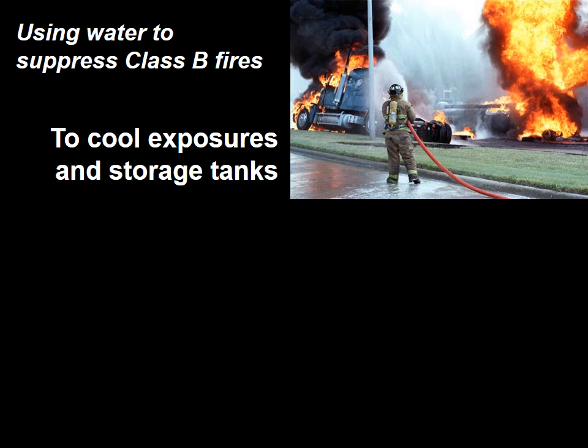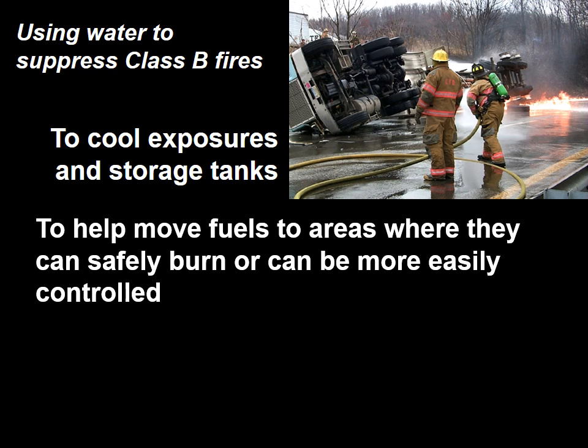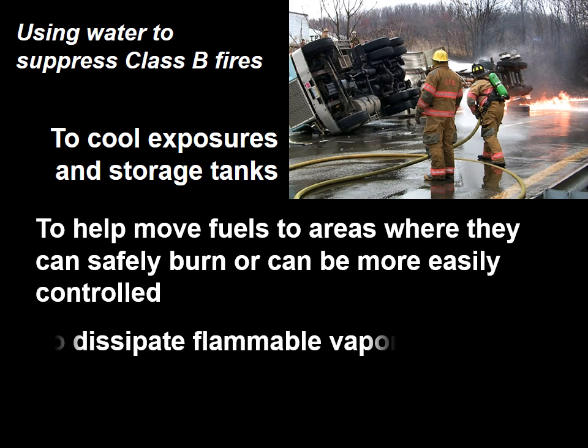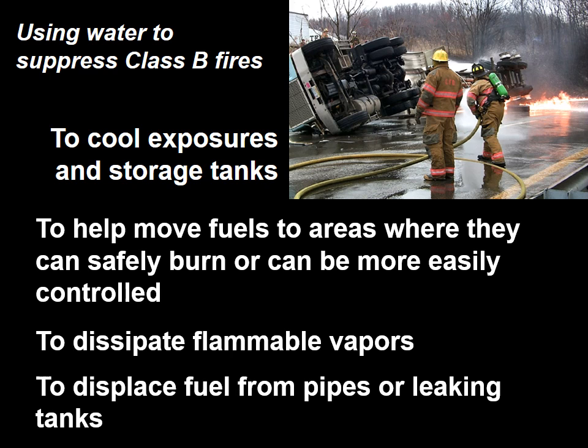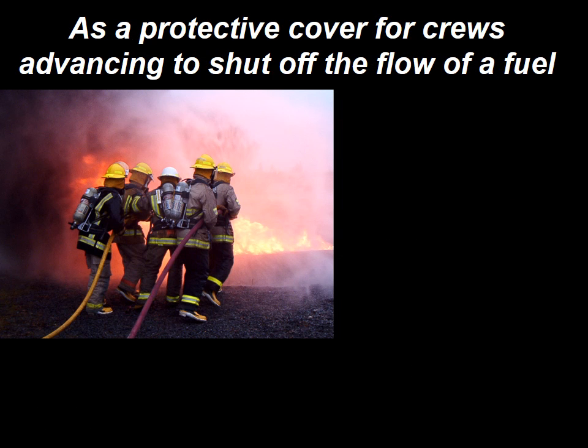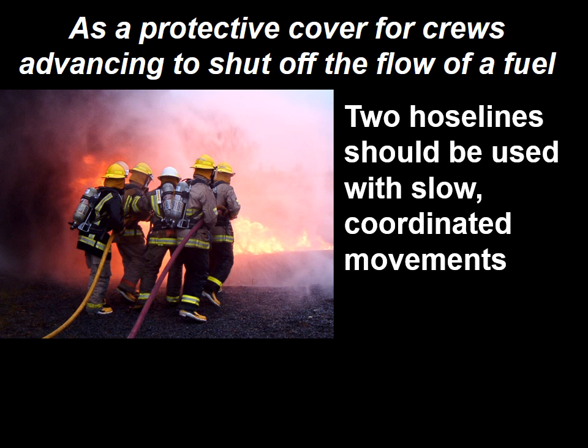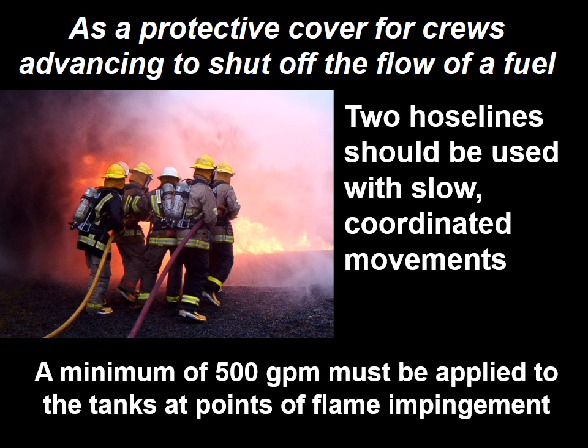Use water to suppress Class B fires, to cool exposures in storage tanks, to remove fuels to areas where they can safely burn and can be more easily controlled, to dissipate flammable vapors, and to displace fuel from pipes or leaking tanks. As a protective cover for crews advancing to shut off the flow of the fuel, two hose lines should be used with slow, coordinated movements.